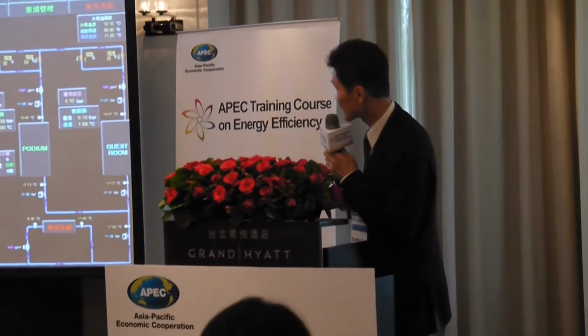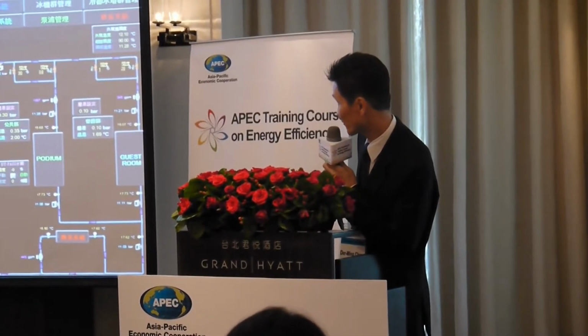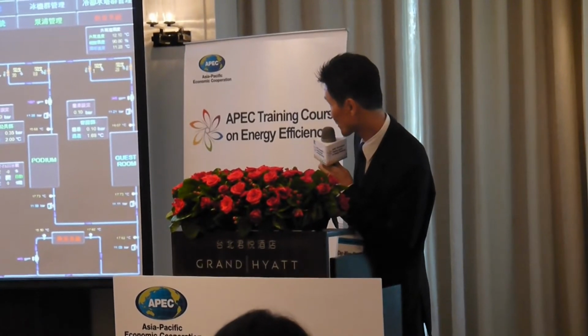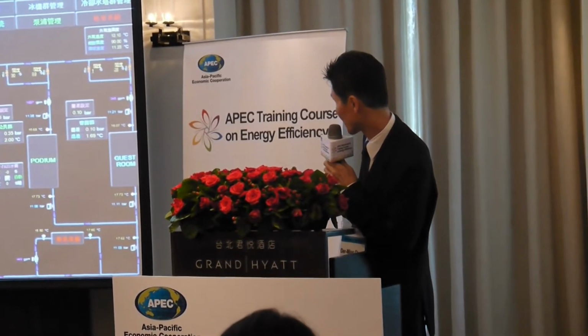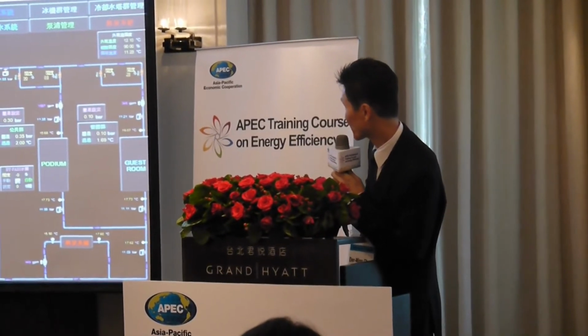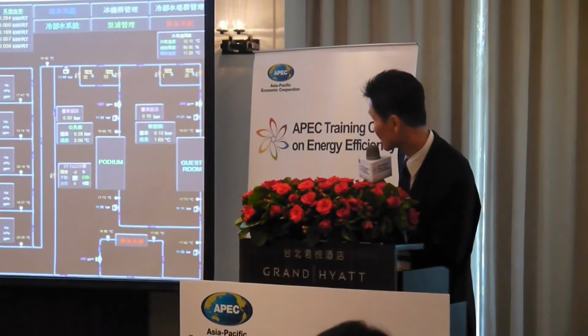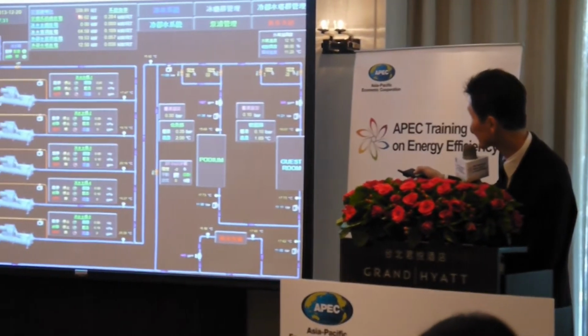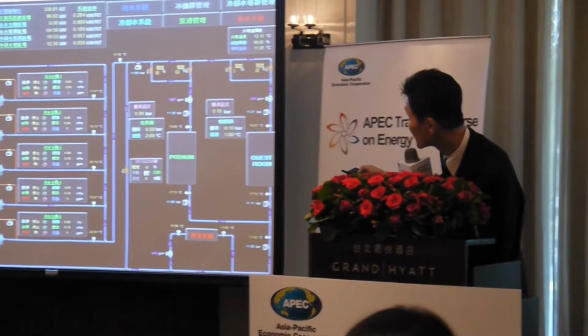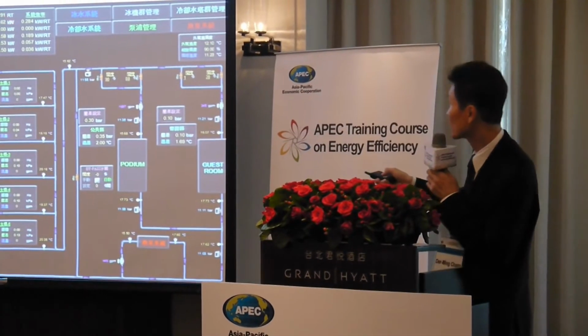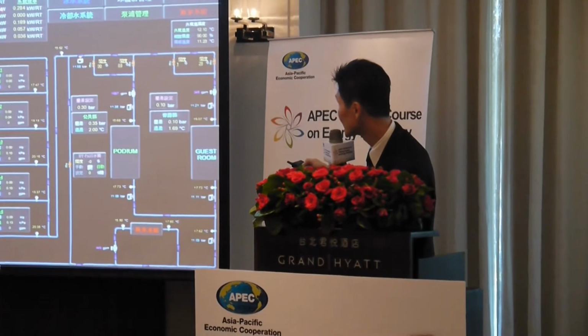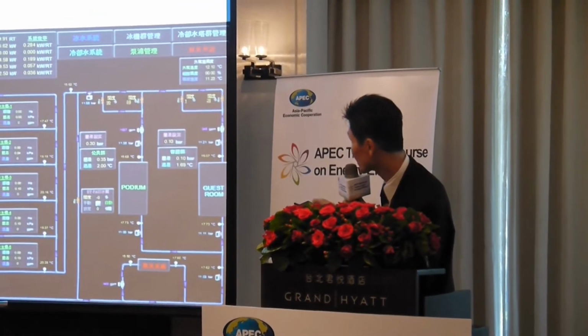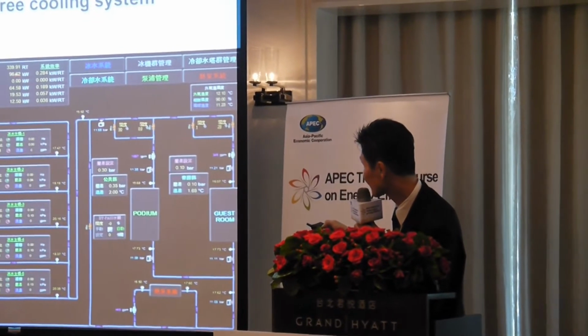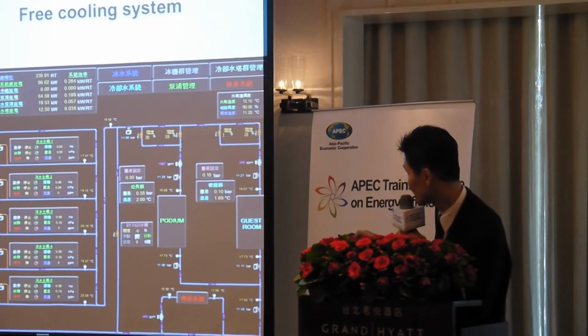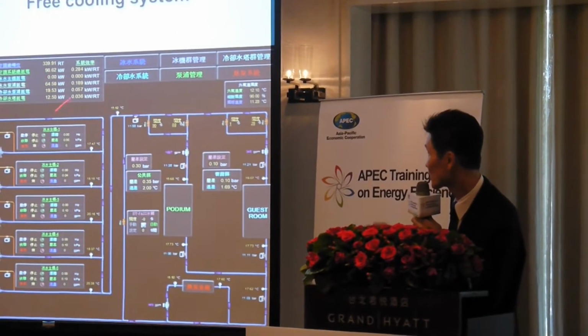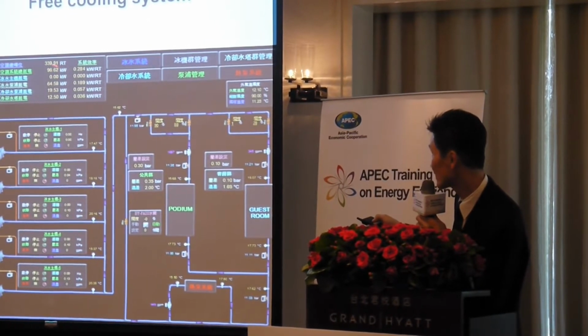Here is our free cooling system. In the normal circuit, the chilled water pump flows through the chiller and produces chilled water to the guest rooms. But in the winter time, like currently, we just stop all the chillers. Here is last year December. In the afternoon, the hotel aircon loading is 339 tons, and the aircon system consumption is 96 kilowatts. But the most important thing you see here is our chiller consumption is 0. That means we don't run the chiller, but we still get the 339 tons of aircon.